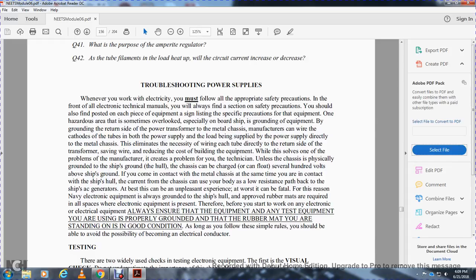This solves one of the problems for the manufacturer, but it creates one for you, the technician. With the chassis physically grounded to the ship's hull, the chassis can be charged and can float at as much as 100 volts across the ship ground. If you come in contact with the metal chassis at the same time you come in contact with the ship's hull, the current in the chassis can cause your body to become a low-resistance path back into the ship's AC generator. At best, this can be an unpleasant experience. At worst, it could be fatal.